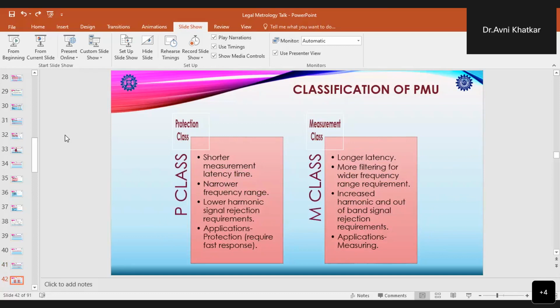Now, when we talk about phasor measurement units, they are classified into basically two different categories, that is P class PMUs and M class PMUs. They are classified in these two categories based on their application, whether they are used as P class, that is protection class PMUs, or M class, that is measurement class PMUs. The P class PMUs have shorter measurement latency time, a narrower frequency range, and lower harmonic signal rejection requirements, and the applications are basically protection type applications which require a fast response. Hence, they have a shorter measurement latency time.